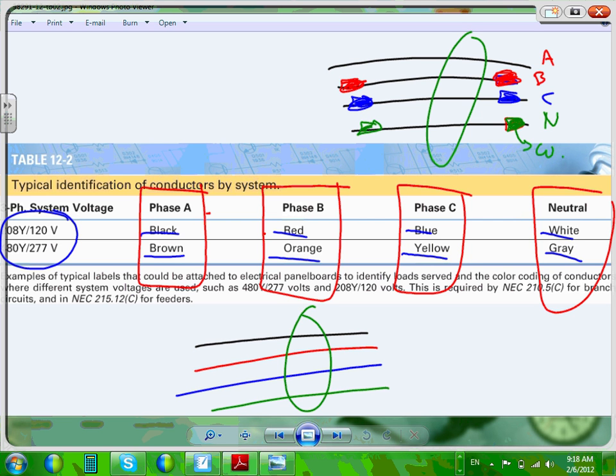A lot of companies that respect themselves have color-coded insulation. It's pricey on feeders larger than number 4. I think number 6 and smaller have to be color coded, but number 4 or larger can be any color. Even the black can be neutral as long as you identify it with a white tape at the end that identifies it as a neutral conductor.